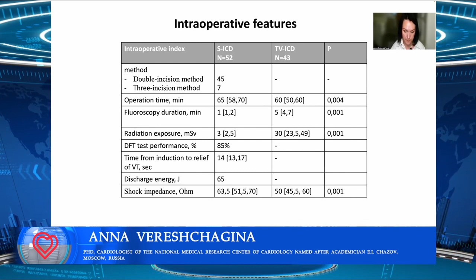All patients with subcutaneous devices underwent defibrillation testing at the end of the operation. Induction of ventricular fibrillation is conducted with a 200 milliamperes, 50 Hz alternating current pulse for 4 seconds. The detection rate is lowered to a minimum of 177 beats per minute. The energy of the first discharge is programmed at 65 joules. In case the first shock is ineffective, the second discharge is automatically programmed to the maximum possible energy of 80 joules with reverse polarity.